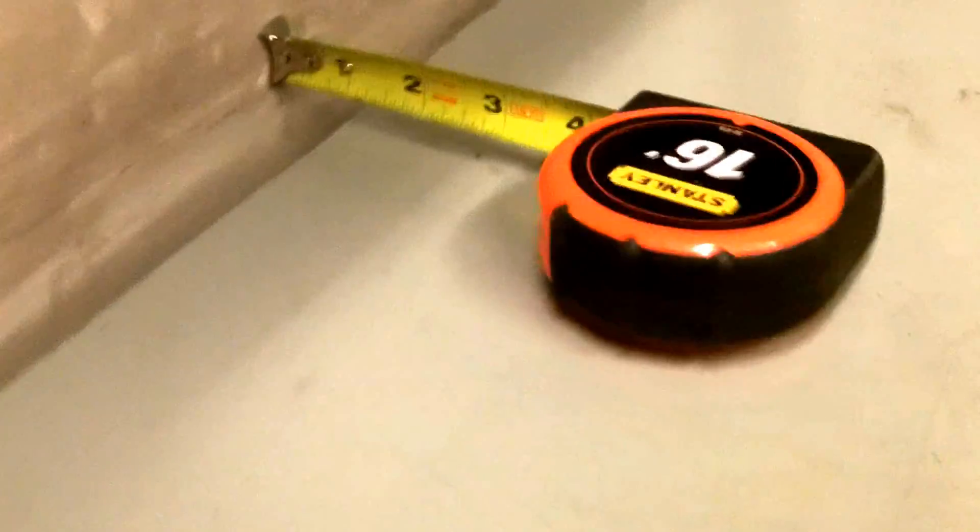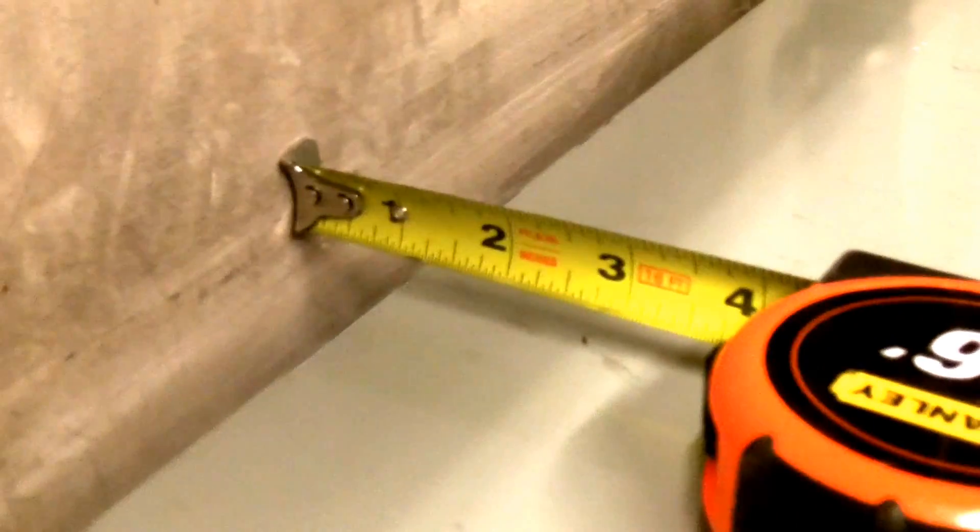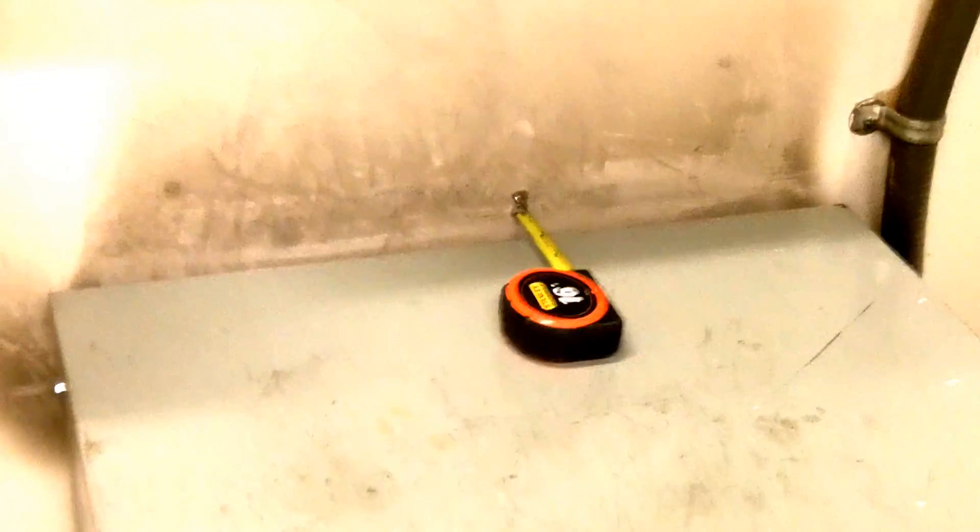If you look in the back, we'll see that there is only about 3 quarters of an inch space between the back of this transformer and the wall. So that back vent opening is blocked, and you can see all the heat marks on the wall.